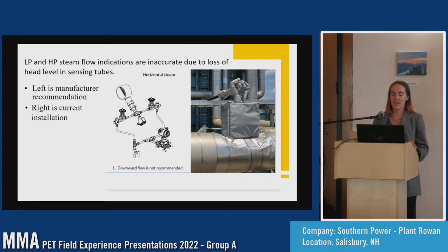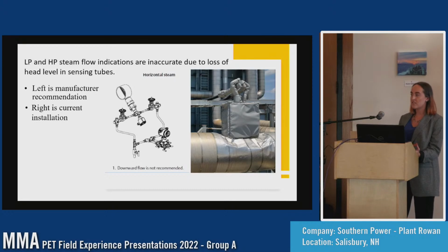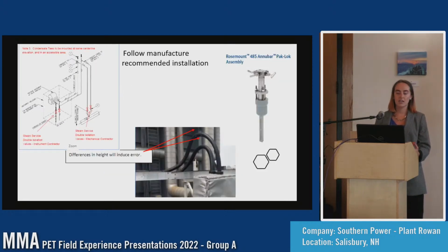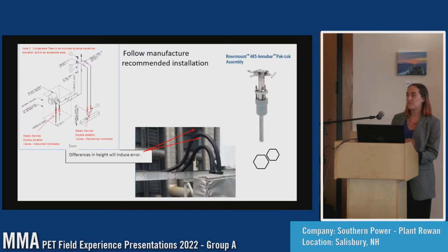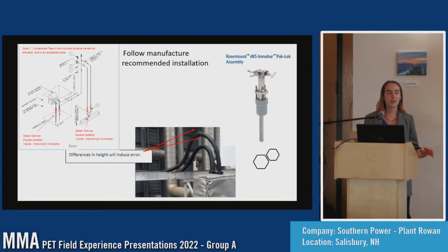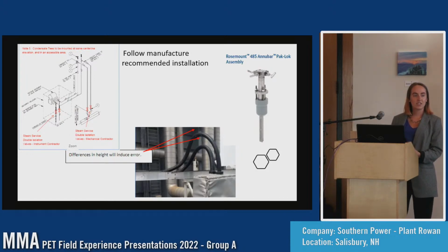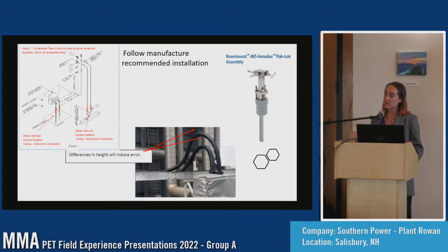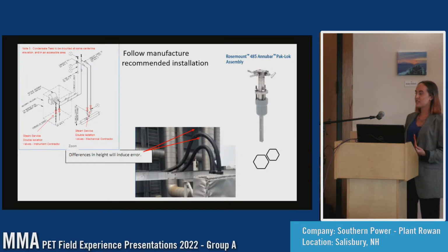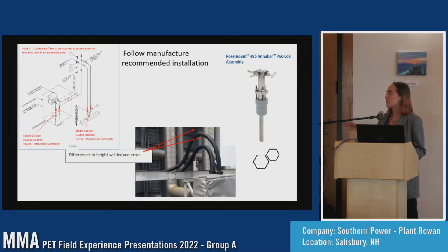Our problem was that the way it was installed in the plant was incorrect. They had tried to fix this before by putting in a second isolation valve, which you can't see, so that they could refill the sensing lines, and they were finding that was not working. I talked and emailed with some Rosemount engineers to help me explain the situation, and they gave me my recommendations. Then I worked with SPS Engineering to see what they would do with it. I was also lucky enough to have, in this bottom picture, documentation from the first time they tried to fix it. Obviously it looks different, and their first fix was just the second isolation valve, and they made the sensing lines, those black tubes there, the same height.